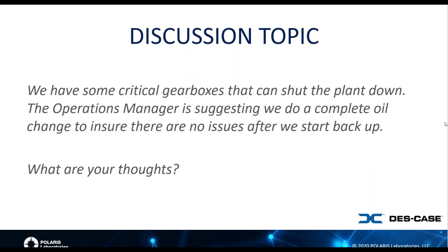Yeah, and maybe Bob, you also want to comment on this a little bit as well. The other thing I would say is when you take an oil sample and you test it for a gearbox, make sure you're running the right tests, because a lot of the failure mechanisms we see in gearboxes generate large particles. In this context, we're talking 5 microns and greater. And the standard test method that we run in the lab, the ICP method for measuring wear particles, typically is only going to measure less than 3 microns. But you may want to comment there about some things that you do in the lab specifically to ensure that we can pick up those larger particles.